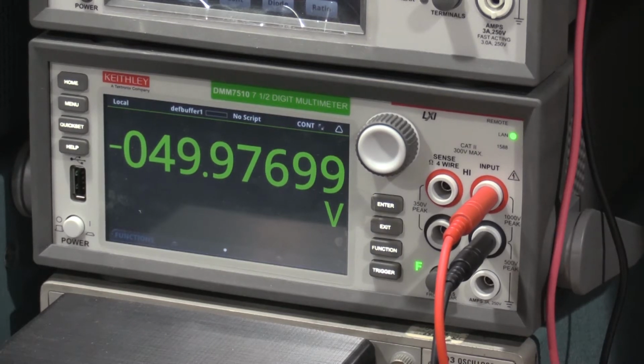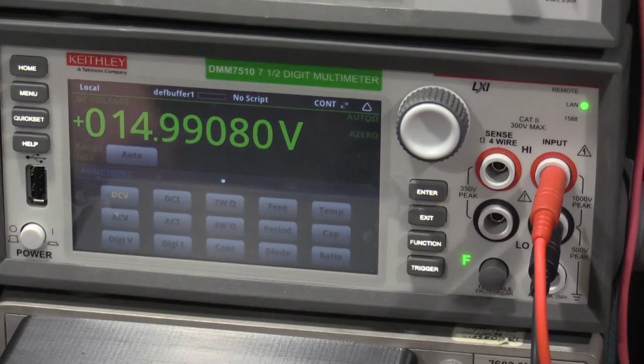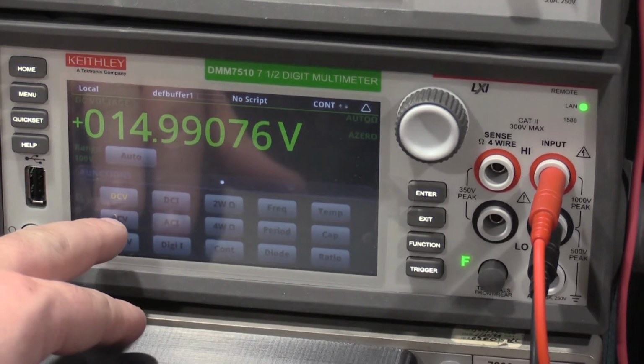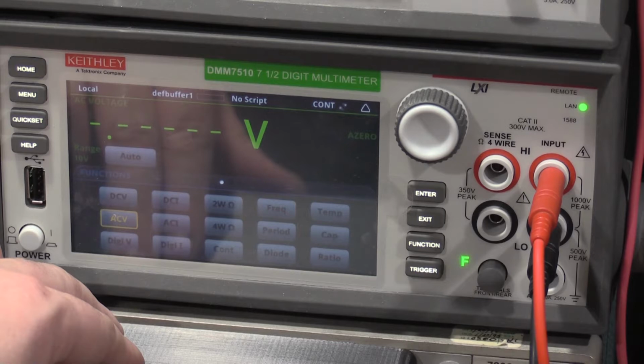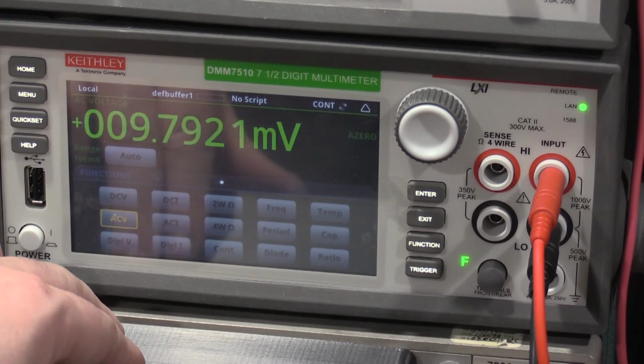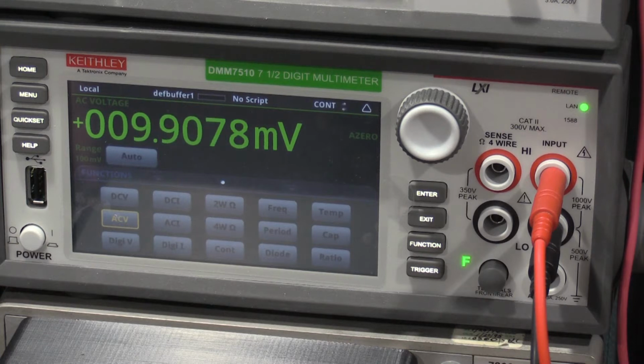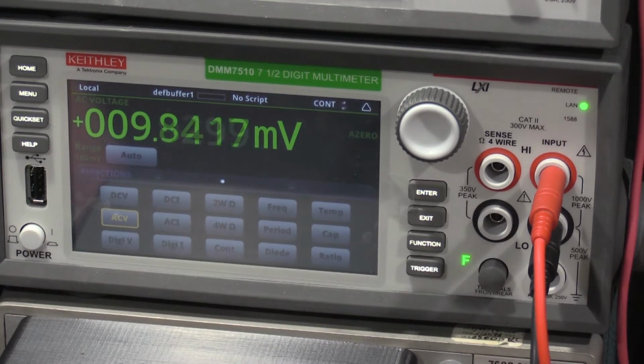One thing to note with these power supplies is the 4-bay frames are a switching supply. The 3-bay frames are usually a linear supply, so they're different. Okay, checking the ripple on the plus 15 volt test point. It's running a little high.